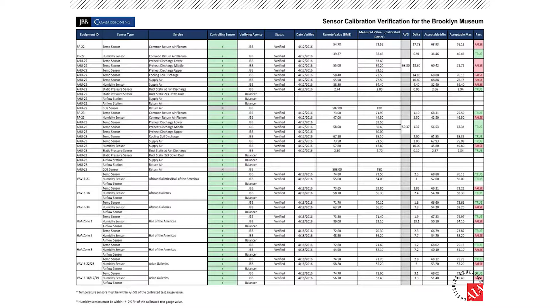After sensor accuracy verification, we moved into functional testing of the individual pieces of equipment. So that's your standard functional testing. We reviewed the sequence of operation and created project-specific forms that went through each aspect of the control for the air handling units. So these are pretty complex units that have a lot of capabilities, right, because of the nature of the project. We're talking humidification, dehumidification, temperature control, static pressure control, interlock, lead-lag sequencing between the headered units, and of course safeties and alarms. So there was a lot to go through.